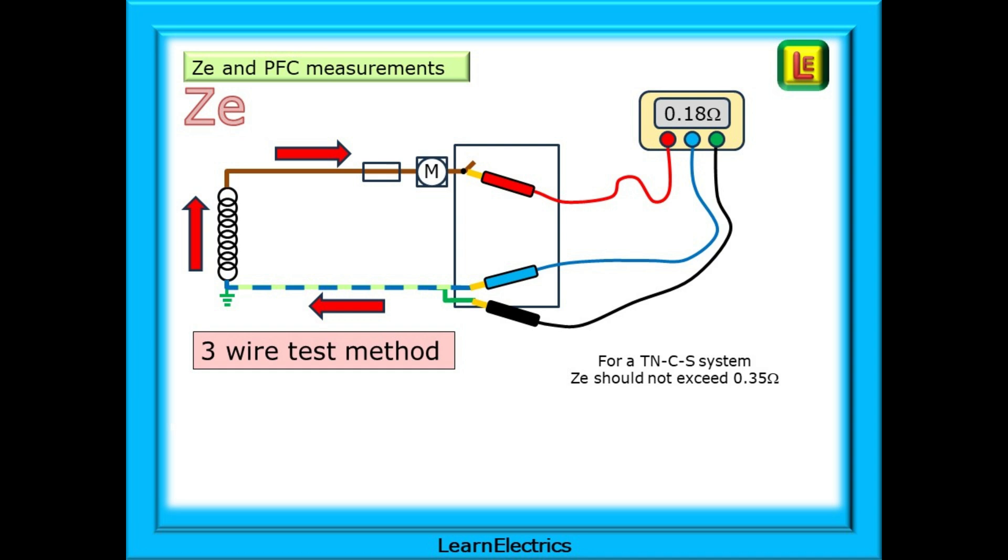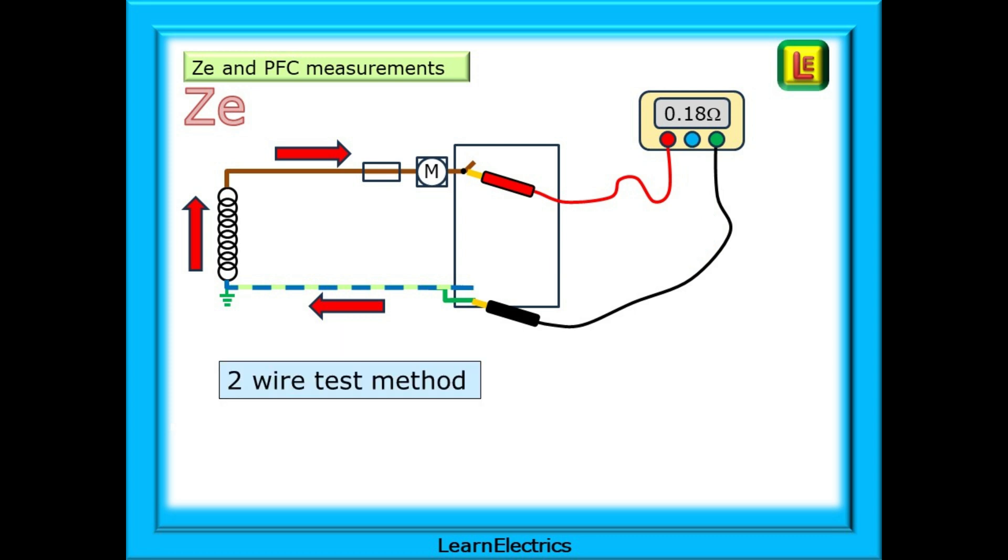This is the only ZE for this installation. For a TNCS system as shown, ideally this should not exceed 0.35 ohms. Some test meters can test using only two wires. They do not need the neutral test lead to be connected. And in theory we should get the same reading for ZE. Whichever meter type you have, ensure that you know how to use it before your assessment day. Practice, practice and practice some more. The time to learn how to do the tests is now, not when you are stood in front of the assessor.